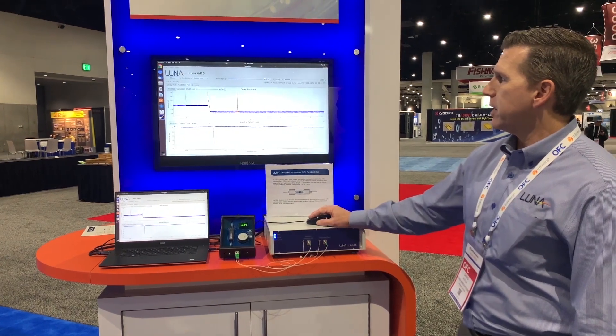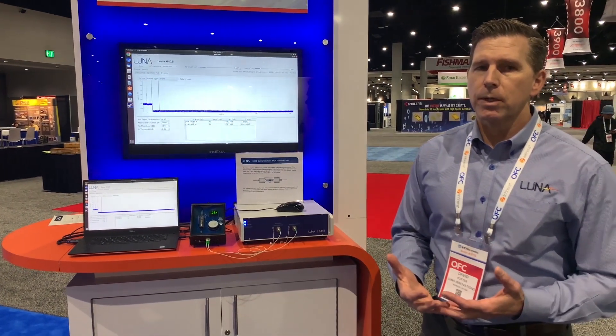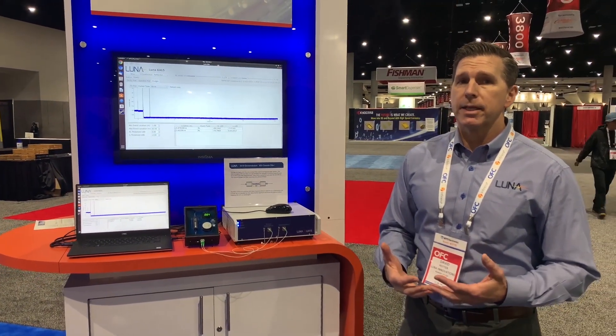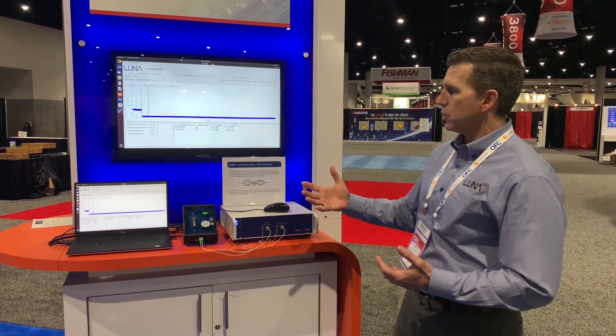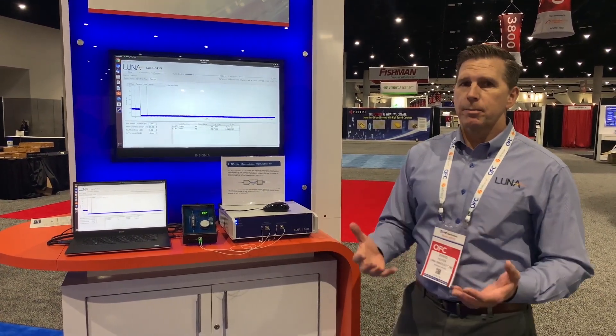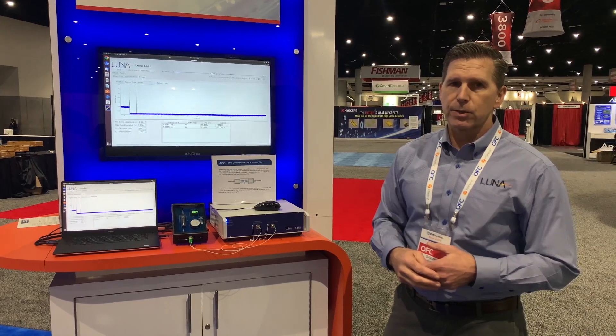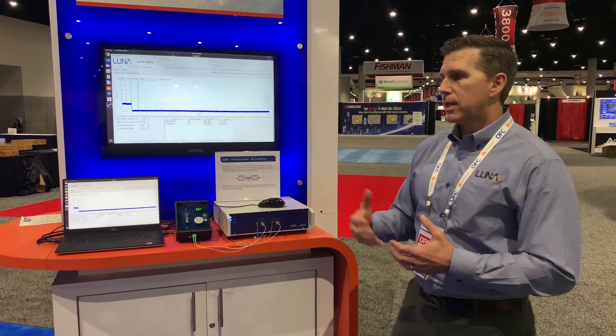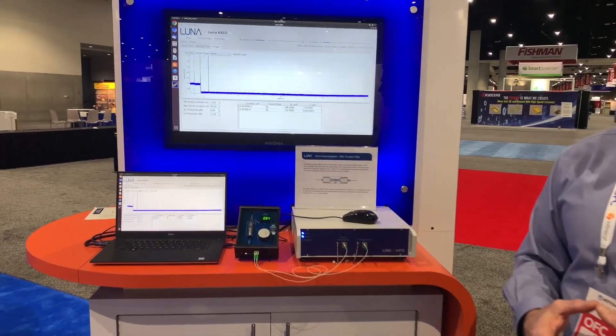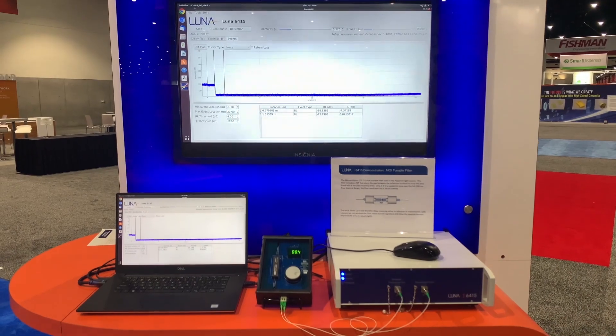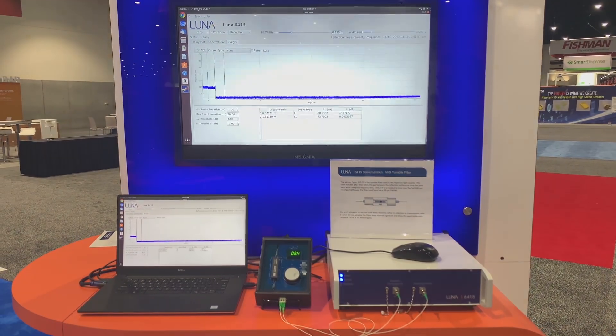The 6415 also provides automated calculation of return loss and insertion loss, comparing to three user-defined thresholds. This is for automated analysis, which is a requirement for a lot of manufacturing test applications.